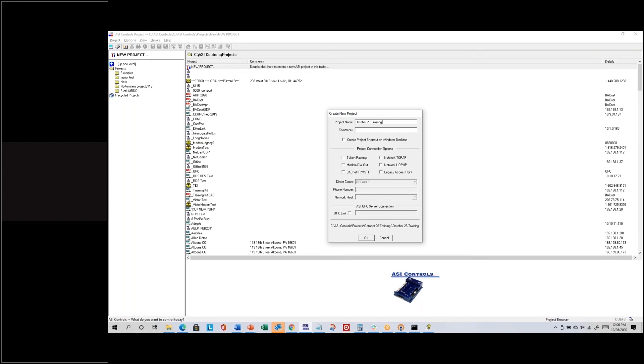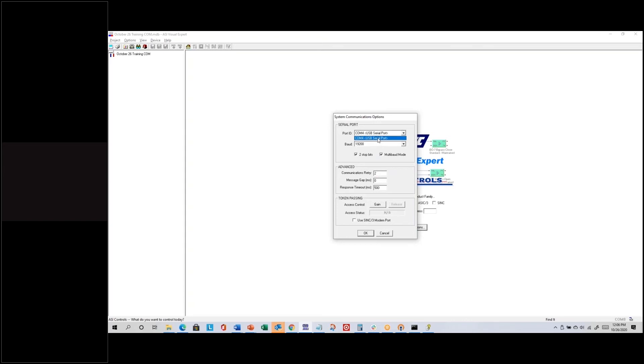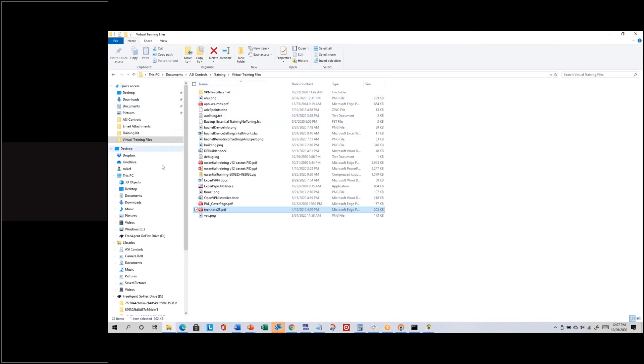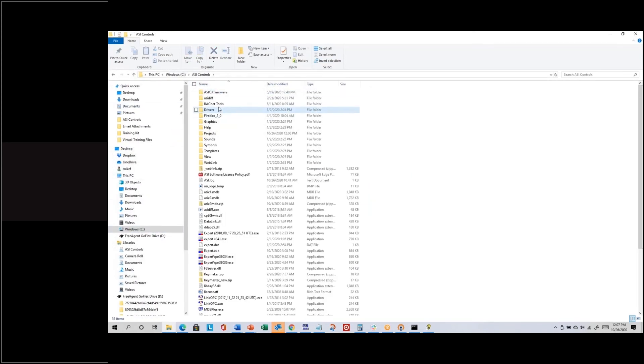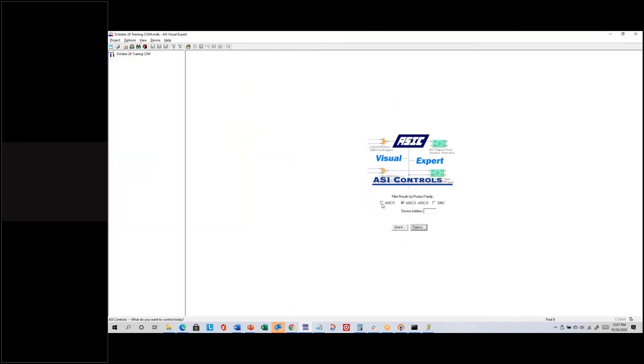I'll call it October 26 Training COM. If I don't select any connection options, it's a COM project — not Ethernet, not telephone modem, not BACnet, just going through a COM port. I click OK. Then I'll go to the Options button. It should install as a USB serial port automatically on Windows 10. On Windows 7, you can go through Device Manager and point it to the Drivers folder installed with ASI Expert to find the needed driver.